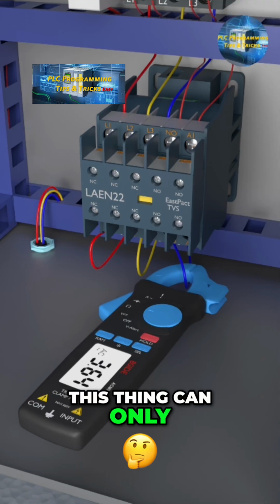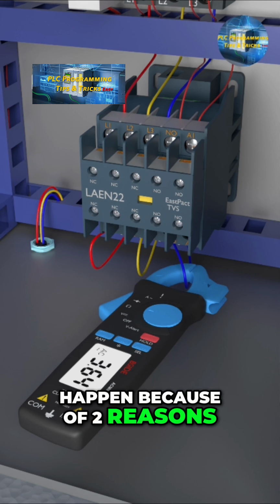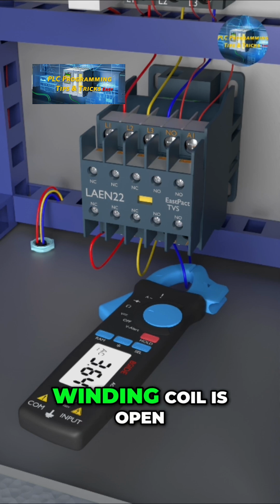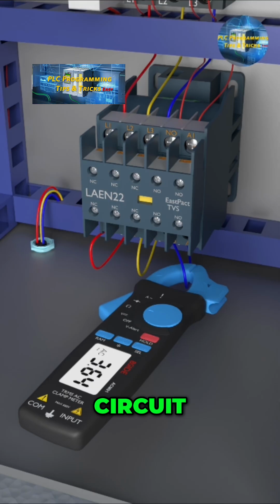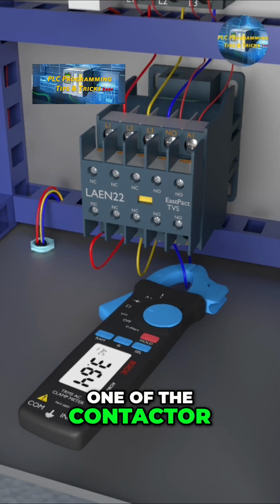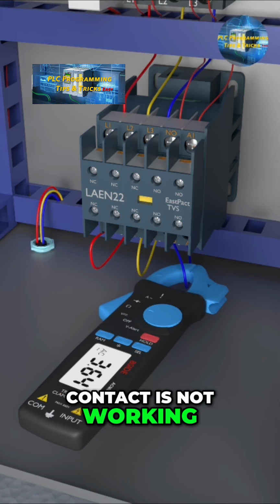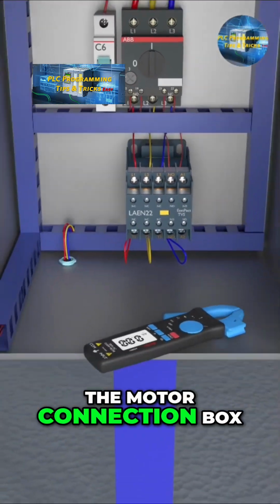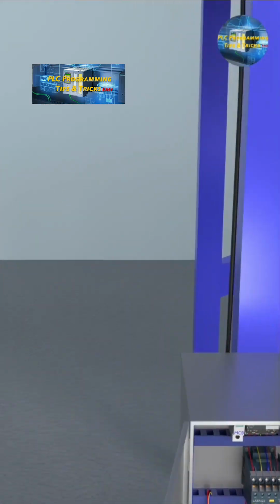This can only happen because of two reasons. Number one, the motor winding coil is open circuit. Number two, one of the contactor contacts is not working. To check further, we will go to the motor connection box and open it.